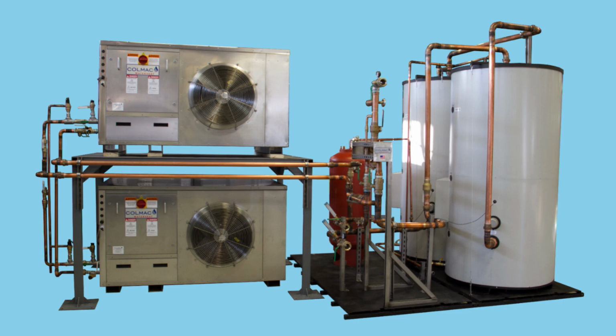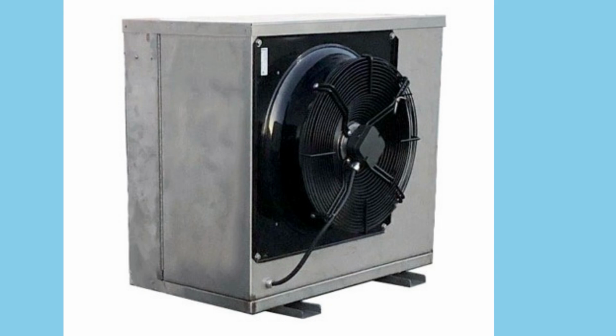When designing a central heat pump water heating system, equipment layout is just as important as system design. The way you locate compressors, storage tanks, and supporting components can make the difference between smooth operation and long-term headaches. Locating heat pump. Most HPs are installed outdoors, but in cooler climates, parking garages can be an excellent option.